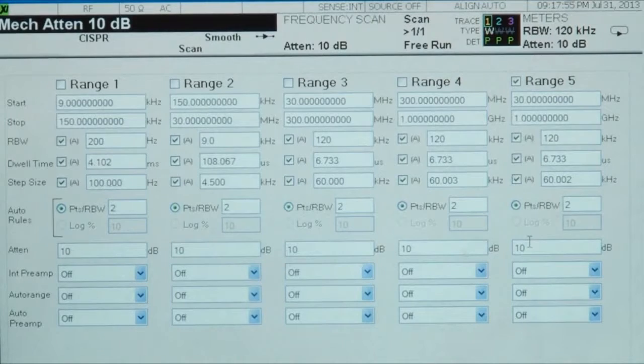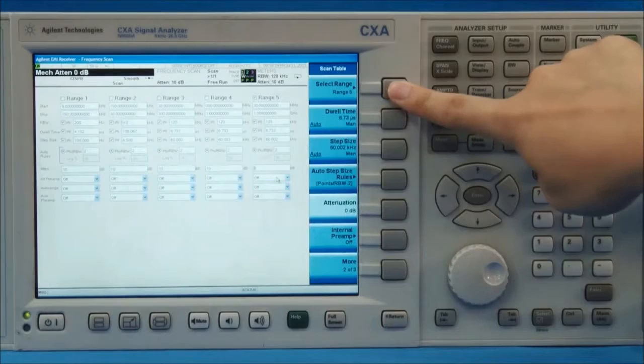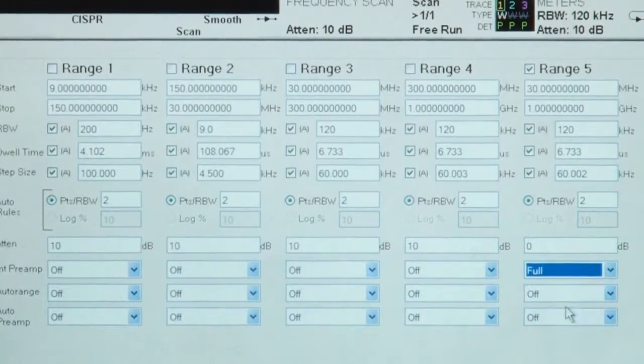As mentioned, radiated emissions are usually low-level signals. Therefore, we set the spectrum analyzer to its best sensitivity. Set attenuation to 0 and enable the full pre-amplifier.